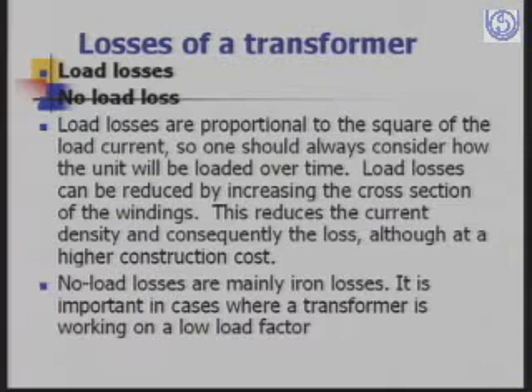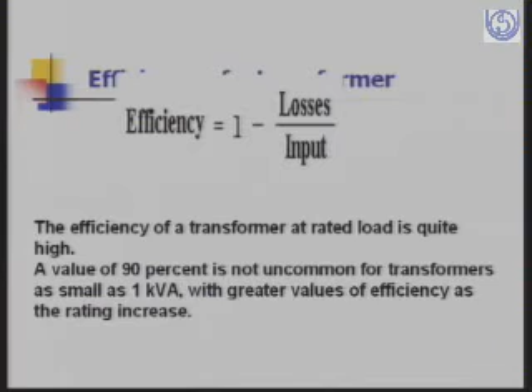And usually the efficiency of a transformer is very high, and a value of 90% is not uncommon for transformers as small as 1 kVA. And these efficiencies increase as the rating increases. For the power transformers, these are in the range of 99% and higher, and even for distribution transformers, these are in the range of 98.5 to 99.5%, depending on the rating and whether it is an oil-filled or a dry type transformer.